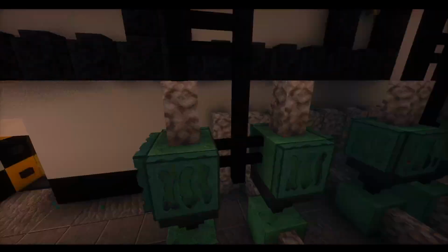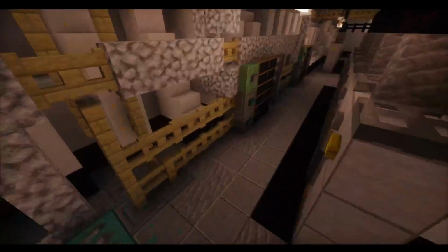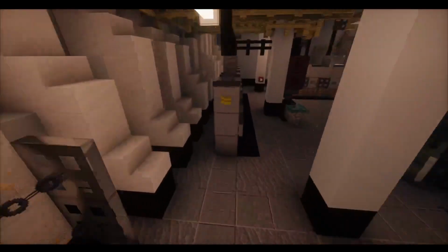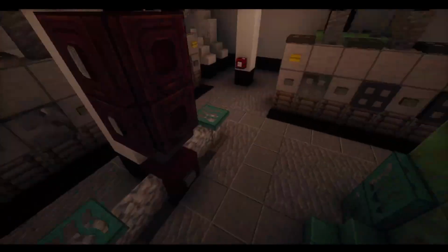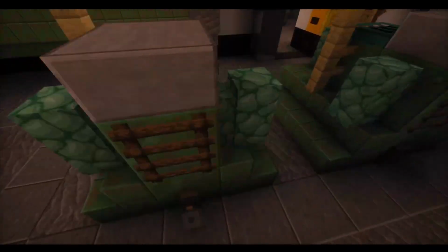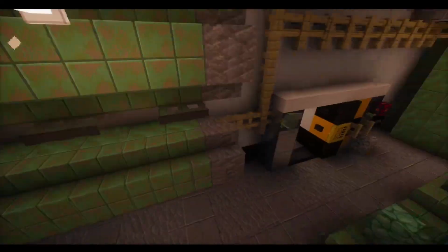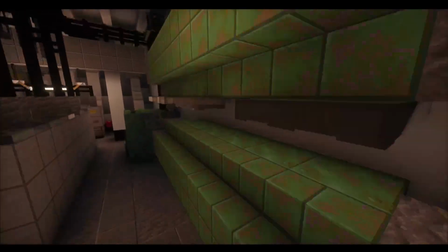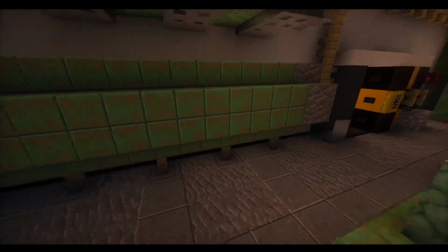Next is the next engine room. It's the same as the other engine room. Here we have coolers. We have some switchboard. Here we have a fire pump again. But here we have the air bottles for starting the engines. The engine is so big you can't start it with an electric motor, so you need air. So here we have the air compressors, three of them, and this is going to these air bottles. These are the air bottles, and we have service bottle and work bottle.